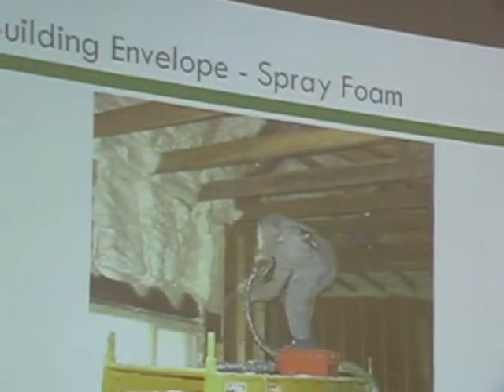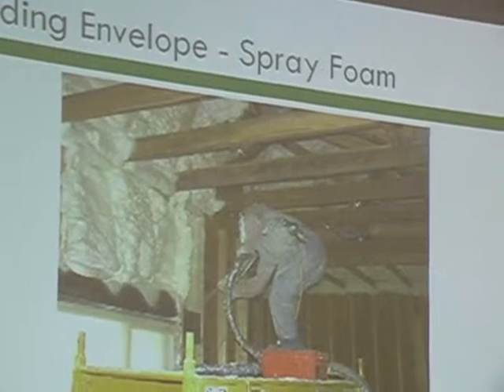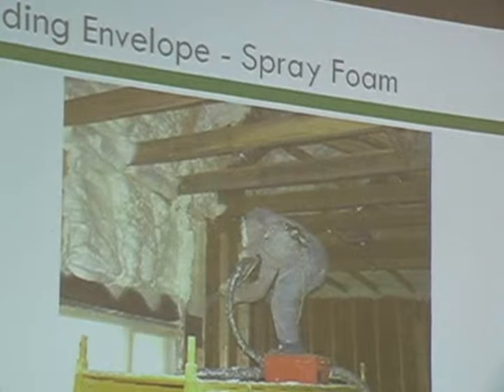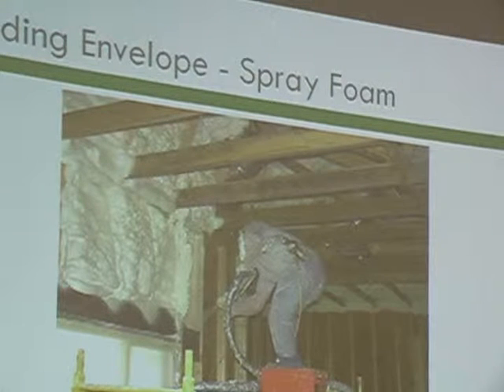Here's some of the spray foam that's done on site. Basically, we're spraying the walls and then spraying the rafters — spraying the top — because all of our air conditioning ducts are inside that conditioned space. In our model house, we put up a thermostat where the attic access is, with a piece of glass, and it never got above 78 degrees all summer. Compare that to an attic in Texas in the middle of summer at 140 degrees — we're trying to push 70-degree air across a house through 140-degree air with only half-inch foam around the ducts. We need to start thinking smarter.